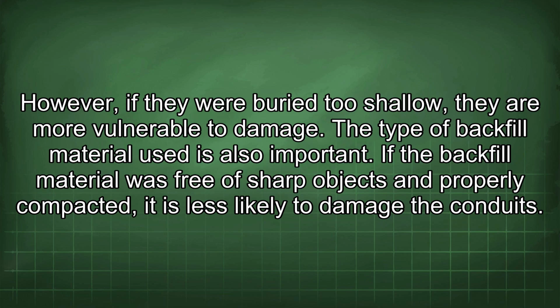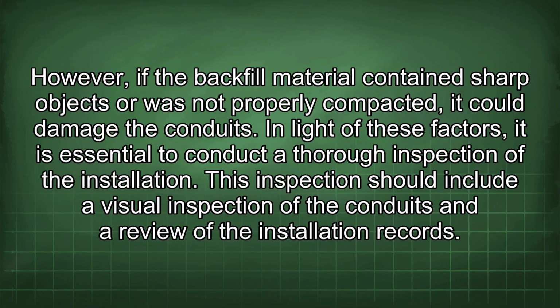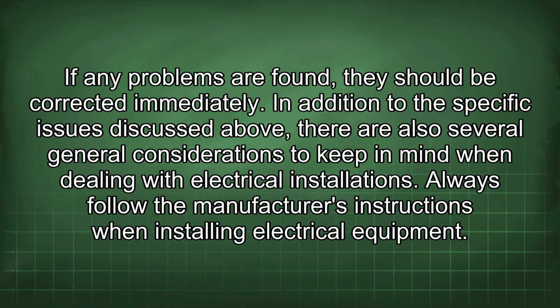The type of backfill material used is also important. If the backfill material was free of sharp objects and properly compacted, it is less likely to damage the conduits. However, if the backfill material contained sharp objects or was not properly compacted, it could damage the conduits. In light of these factors, it is essential to conduct a thorough inspection of the installation. This inspection should include a visual inspection of the conduits and a review of the installation records. If any problems are found, they should be corrected immediately.